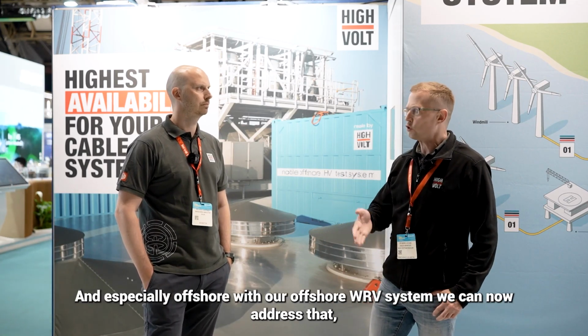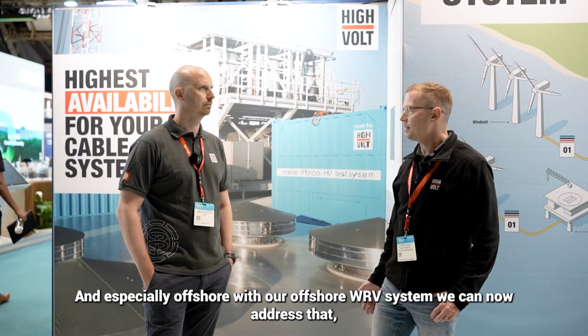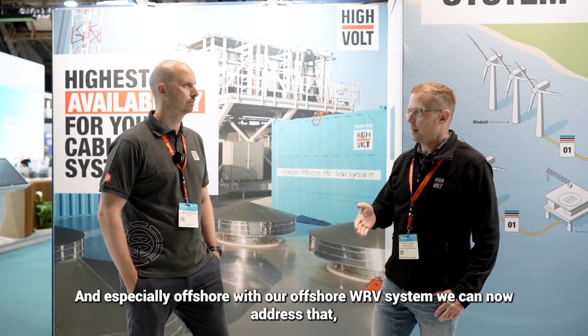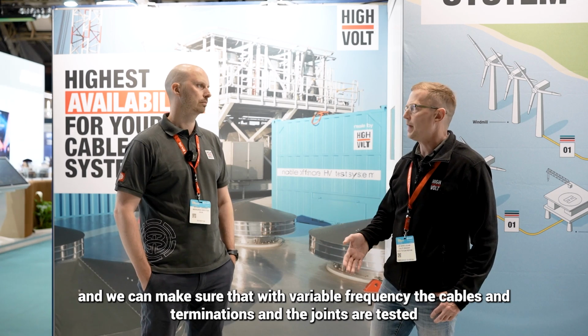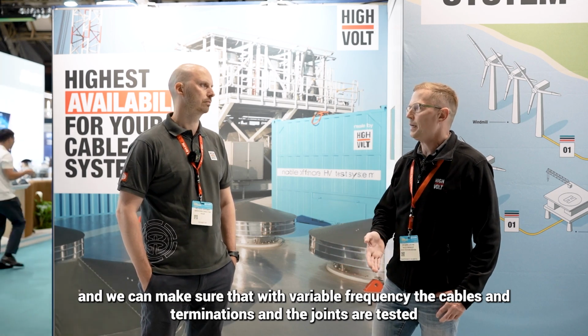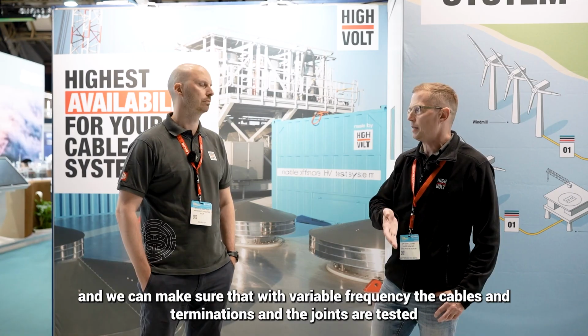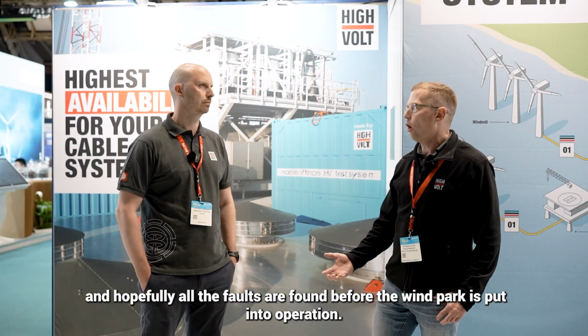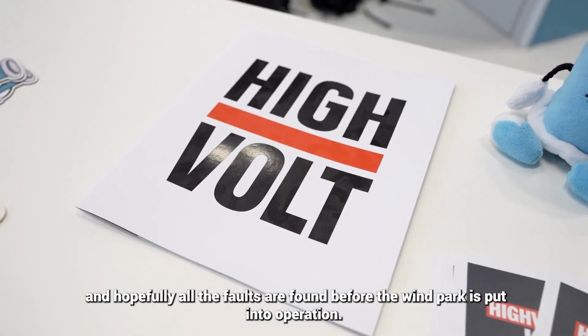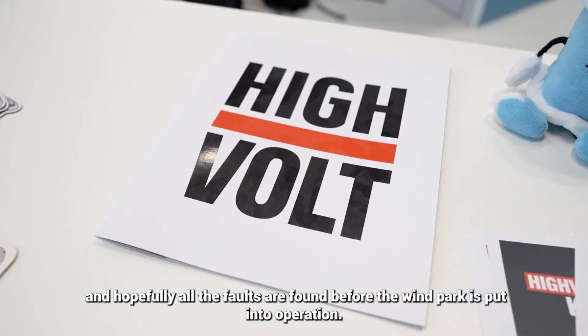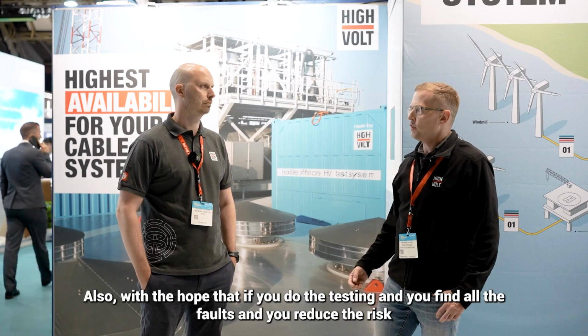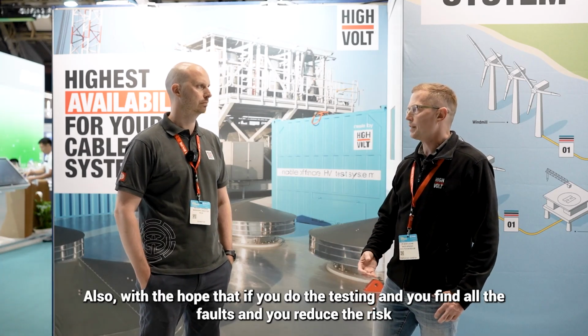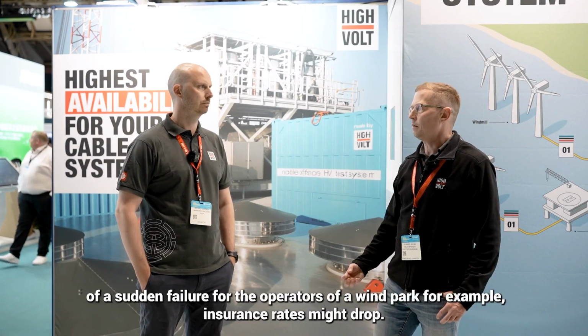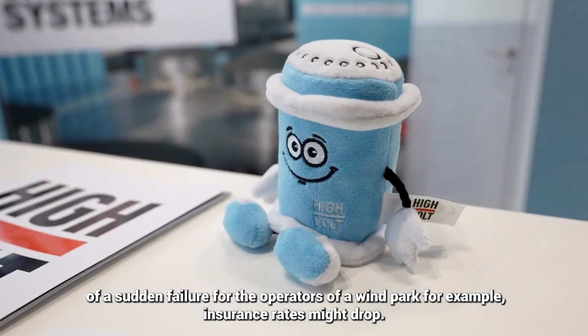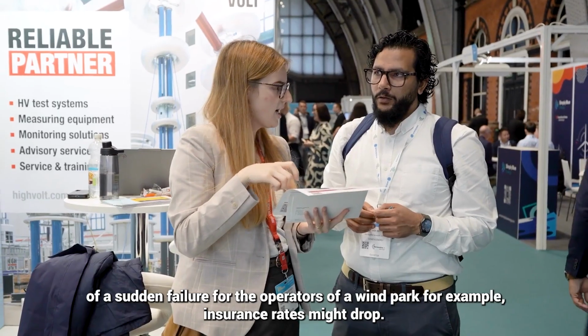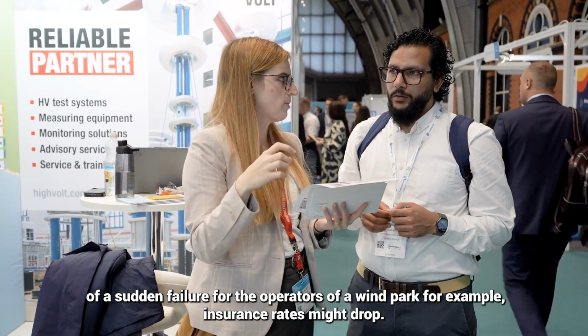And especially offshore, with our offshore WRV system, we can now address that, and we can make sure that with variable frequency, the cables and the terminations and the joints are tested, and hopefully all the faults are found before the wind park is put into operation. Also with the hope that if you do that testing and you find all the faults and you reduce the risk of a sudden failure for the operators of the wind park, for example, insurance rates might drop.